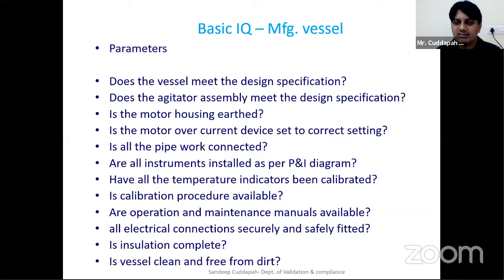For that agitator or mixer, whatever motor is connected, you verify that the motor earthing is done. Then whether the motor overcurrent device is set to the correct setting or not. For any equipment installation, these are called a punch list. They will verify these minimal requirements, whether they are met or not, under each equipment during its installation qualification.